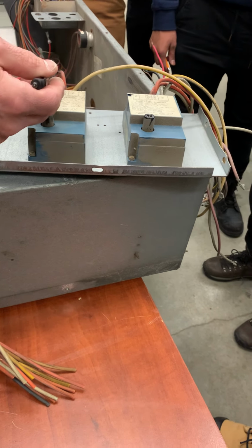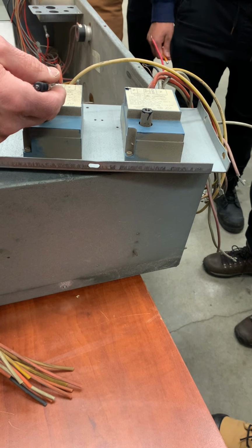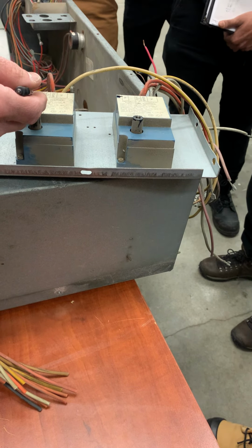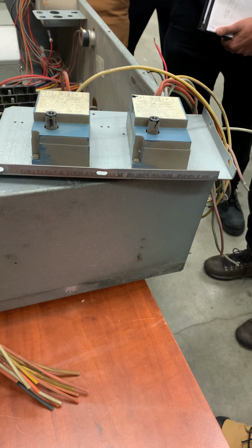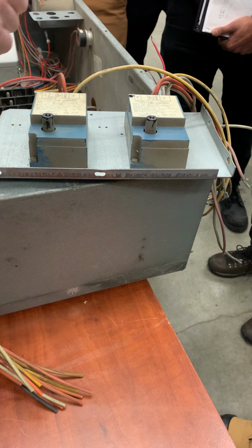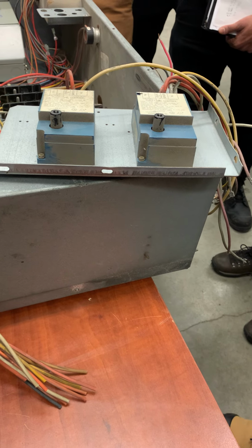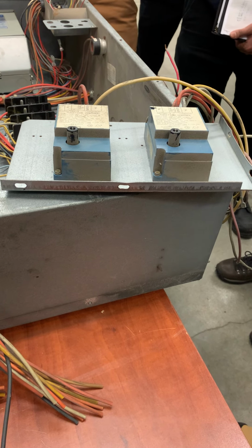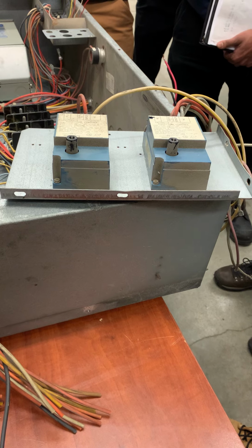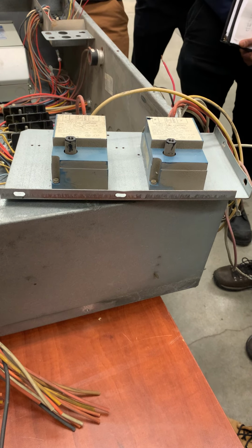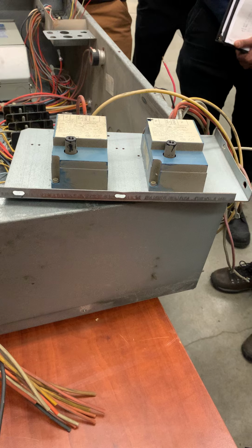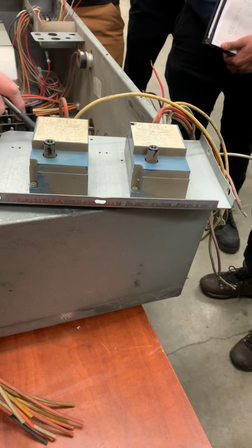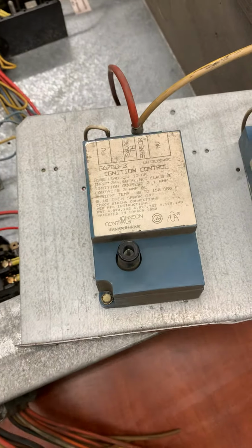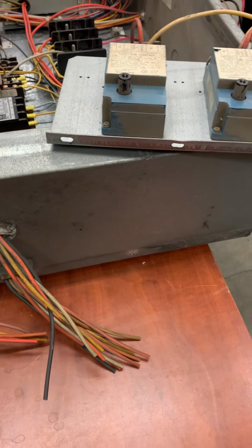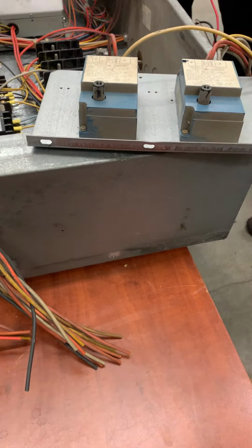Now I'm seeing my thermostat, 24 volt thermostat. I'm seeing main valve, pilot valve. I'm seeing my sensor. I don't have a ground here, do I? Why? Because the ground is the metal backing. So this one, the metal backing, that's my ground. That means the sheet metal is the ground on my 24 volt side.